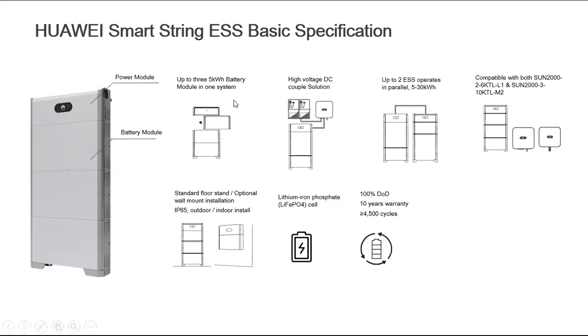This battery is a high voltage DC solution. You can also parallel two power modules to make the battery system up to 30 kilowatt hours. This battery is compatible with both the Sun 2000 2 to 6 kTL single phase inverters and the 3 to 10 kTL M2 inverters. It is IP65 rated, good for outdoor and indoor installation. The cells are made of lithium iron phosphate, and the battery has 100% depth of discharge, with a 10 year lifespan and more than 4,500 cycles.